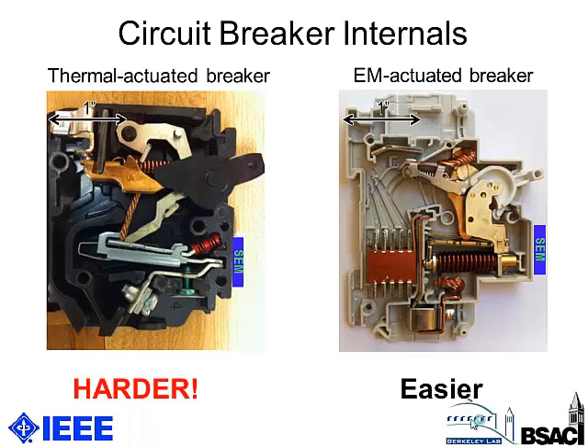And one more thing that I would like to point out here is that in the design of a non-contact based power meter for something like this, the EM actuated breaker is actually a lot easier. And that's because the solenoid in the breaker increases the magnetic field strength in that region by 10 to 20x. So the thermal actuated breaker is a lot harder. Unfortunately, what we've seen is that this type of circuit breaker is a lot more common. So that's the focus of our work, and all the data I present today is measured on a thermal actuated breaker such as this.